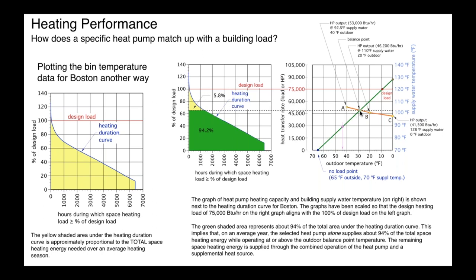And then I drew a line from the balance point across, and you can see the green area down here, which is about 94% of the total area. If we said this yellow area here is 100%, that green area is, in this case, 94.2%. That represents the percentage of the total space heating energy that could be supplied by the heat pump without going into a condition where the heat pump's output is insufficient to heat the building. In other words, at the balance point or outdoor temperatures above the balance point, about 94% of the total space heating energy occurs above the balance point, okay?